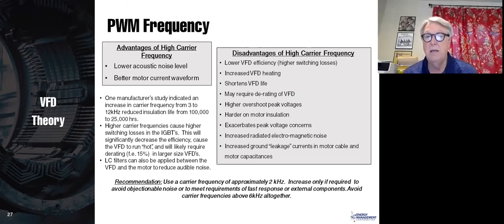My advice, and I think this is advice pretty much that any variable frequency drive manufacturer would give you, is go down to around 2.5 kilohertz. At 2.5 kilohertz, you're kind of hitting that optimum point where you're getting the advantages of high carrier frequency, but you don't get the disadvantages of high carrier frequency.